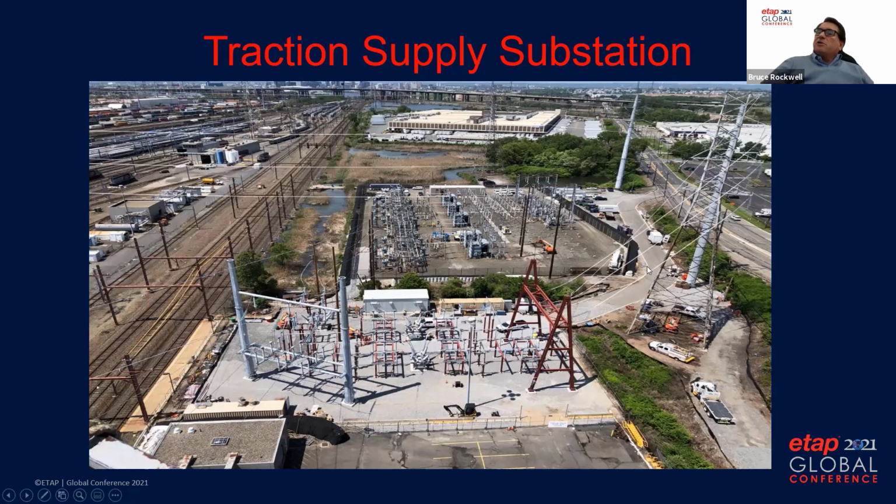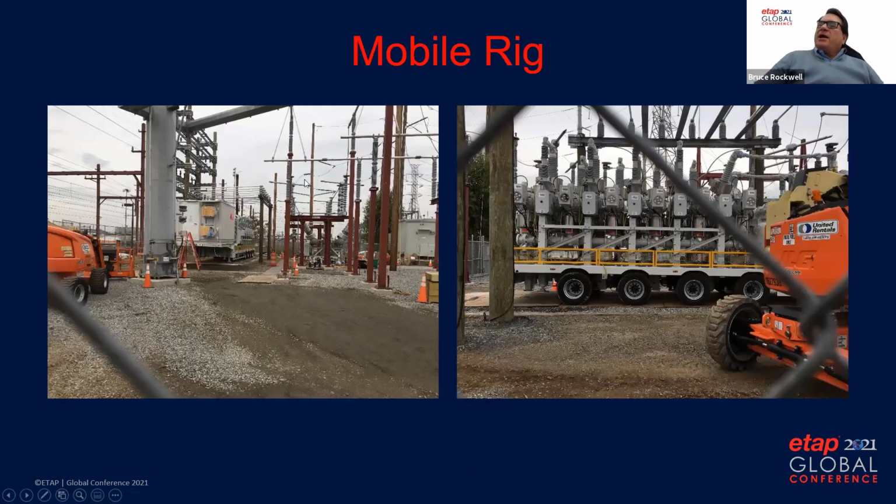And the station is being fed from this temporary 230 kV that goes back to these two supply transformers, which are going to remain. These supply transformers at 230 kV get demolished, and then this half of the auto station gets demolished. You might ask how we were going to run a railroad with half the auto station.